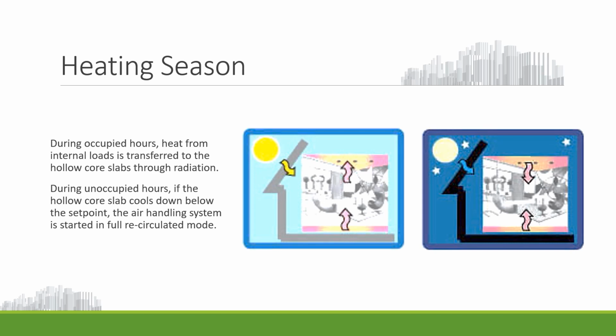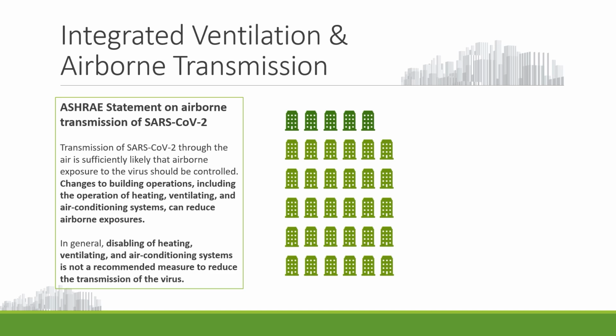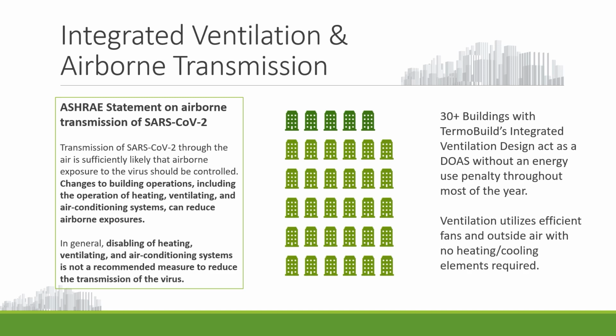So during the day, the heat from the occupants and the equipment is stored in the concrete, and at night, the ventilation system comes on to use that preheated concrete to heat the rest of the building without accessing the heating elements of the HVAC system. And this is how the building can operate throughout the year in fresh air mode versus turning on the heating and cooling elements, which are significantly more costly. One very interesting fact about integrated ventilation design buildings: of the 35 building portfolio that has been built so far, over 30 of the buildings act as a dedicated outdoor air system without an energy use penalty throughout most of the year.